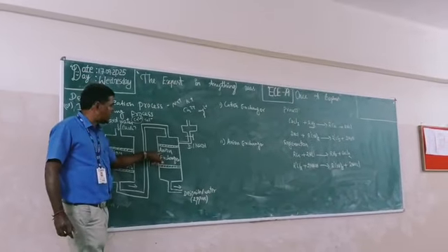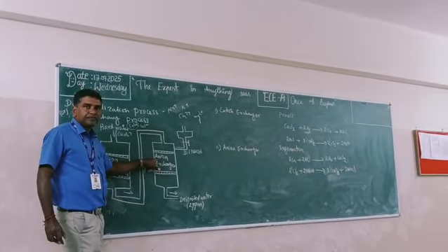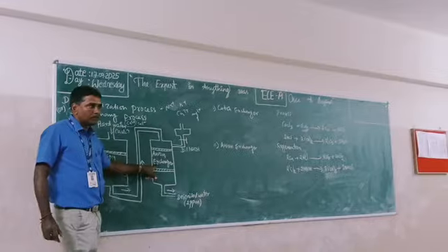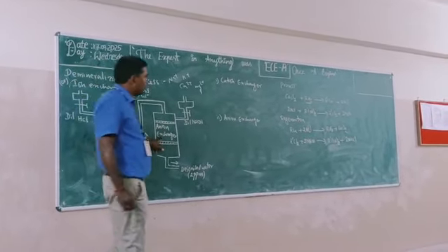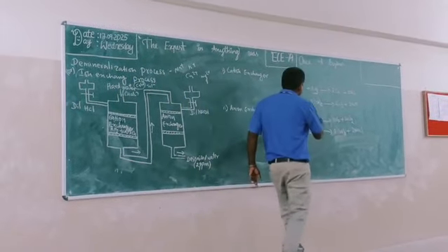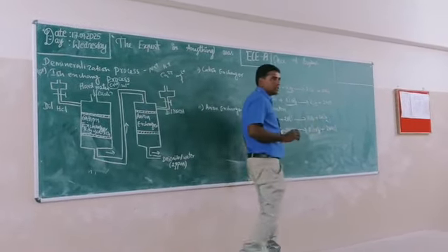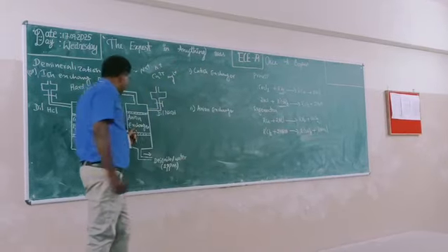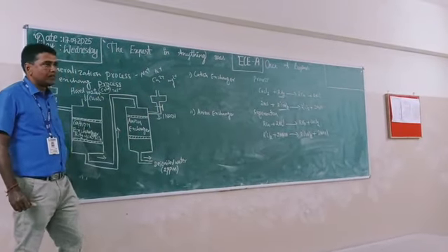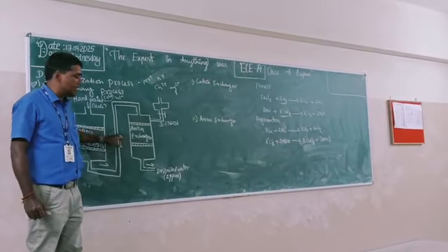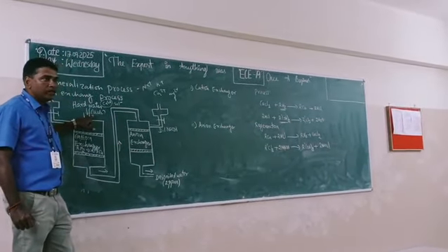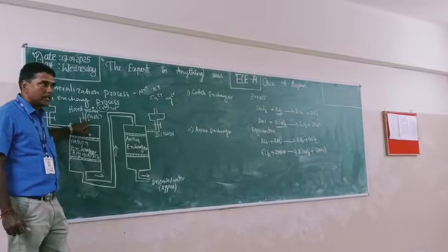The other cylinder is the anion exchange column, or anion exchange cylinder. It contains the anion exchange resin, simply R dash OH twice, which absorbs only the anionic impurities. Cylinder 1 absorbs the Ca2 plus ions, the cationic impurities.